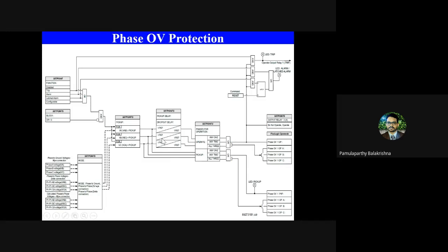Actually, this is a logic diagram of how a protection function is designed in the field. So for example, I am explaining the digital relay logic design of phase overvoltage protection. First thing, I need to define how this function has to behave in the field. Okay, so first, disable means do not take any action when the overvoltage occurs. Trip means trip the breaker by sending a control command to the breaker. Alarm means don't trip the breaker, but only give an alarm to the user that an overvoltage condition has occurred.